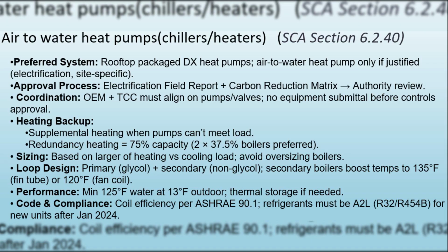From a heating perspective, two types of backup are required. Auxiliary supplemental heating for times when the heat pumps are running but can't fully meet the load. Emergency backup redundancy heating for when the heat pump plant fails entirely. Backup heating must equal 75% of the plant's heating capacity. The preferred solution is 2 electric boilers at 37.5% each. The 3 boilers at 25% each may be used where installation conditions make it necessary. Chiller heaters must be sized based on the larger of the heating or cooling load, not just cooling, to minimize boiler use.